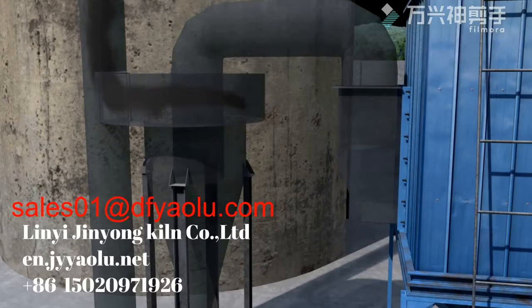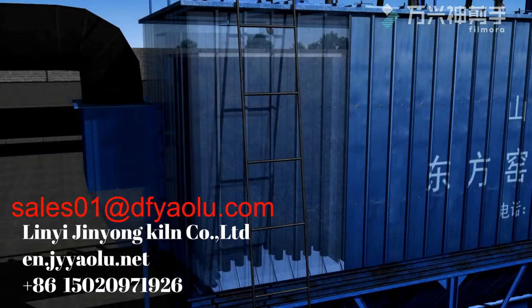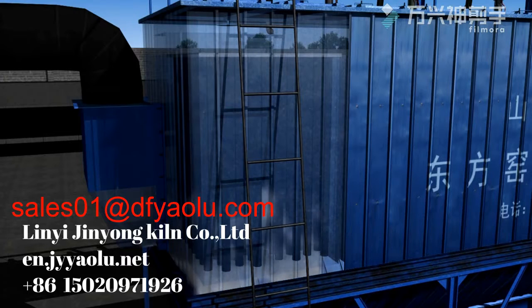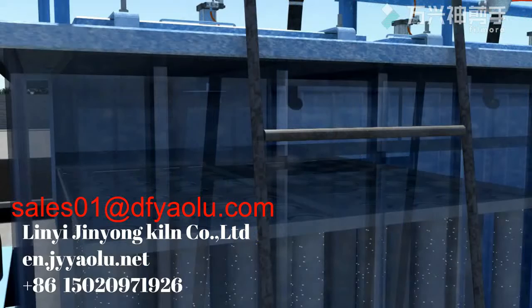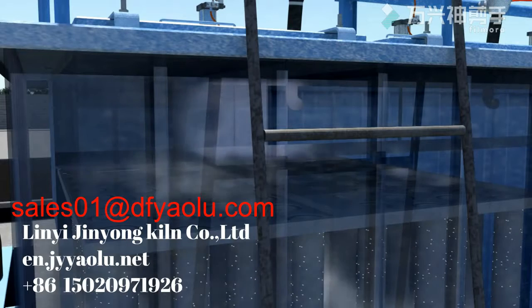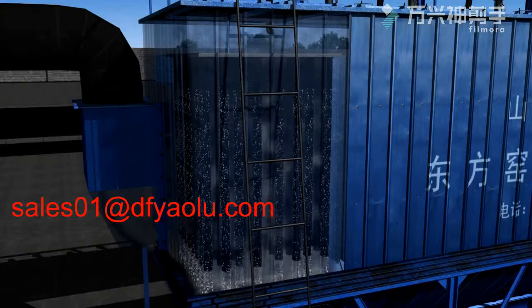Environmental system using 3 stages dust desulfurization technology, composed by first stage cyclone dust removal, second stage high temperature pulse bag filter, and the third stage desulfurization tower. The exhaust gas first go through the cyclone dust removal. Dust in the exhaust gas will be separated out under the centrifugal effect. Then the rest gas go enter the high temperature bag filter. The small particles will be isolated out the bag through filtration, then shaken off by injected gas from pulse valve.